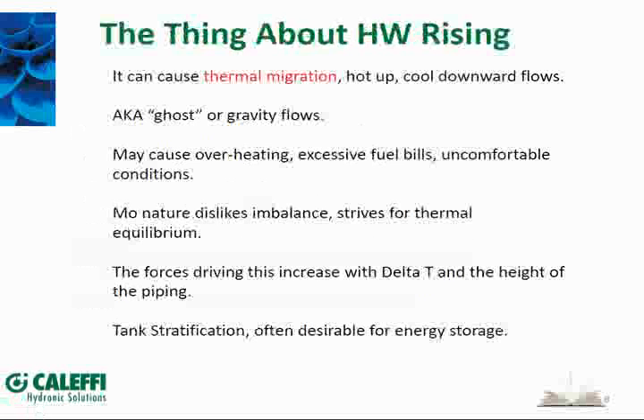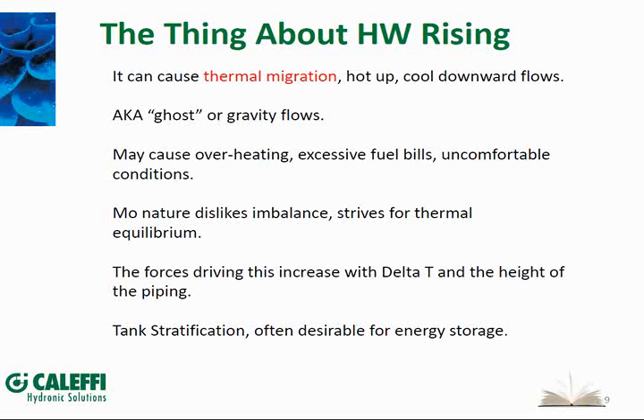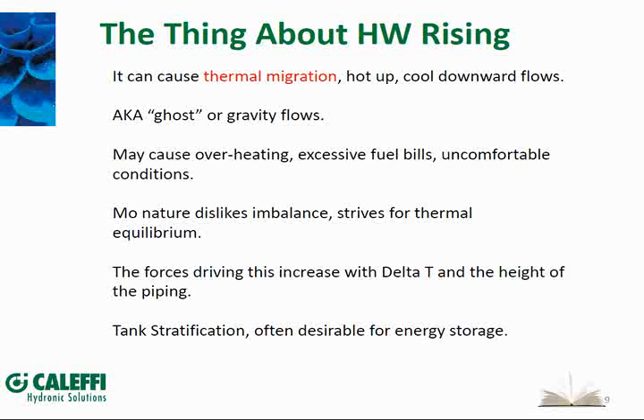Hot water rising can cause thermal migration and actually develop circulation in your system — also called gravity flow or ghost flow. You might experience this in a home where someone says their thermostat is turned all the way down in the bedroom upstairs, yet heat keeps coming out over a couple of days or weeks and the temperature keeps going up. The contractor confirms everything is working right — pumps shut off, zone valves shut off — but there's still some heat coming out.